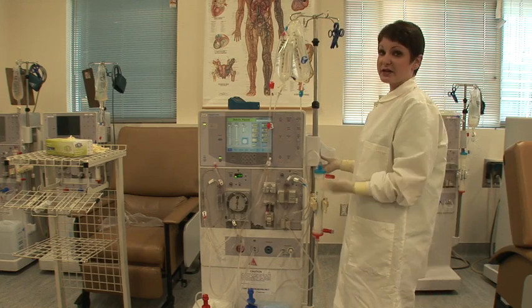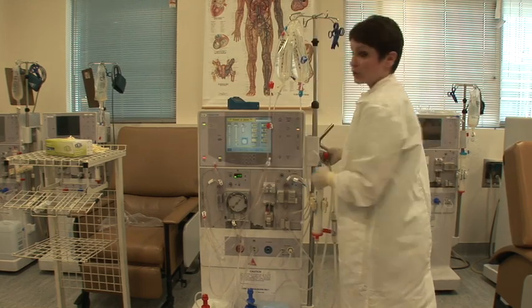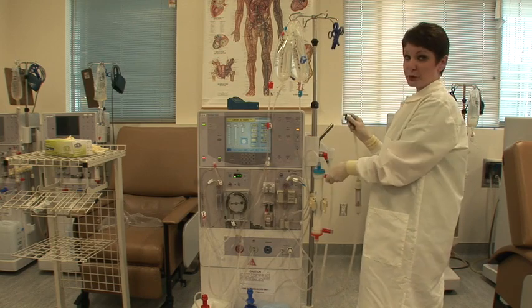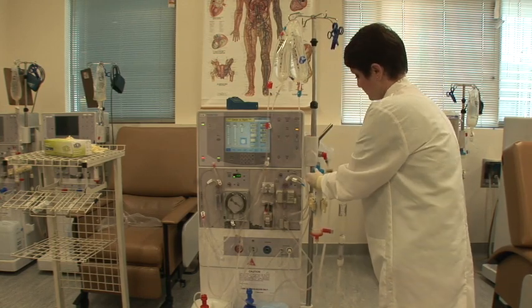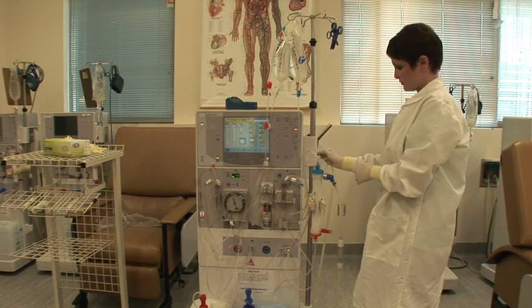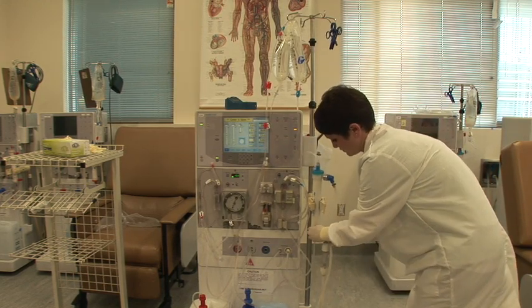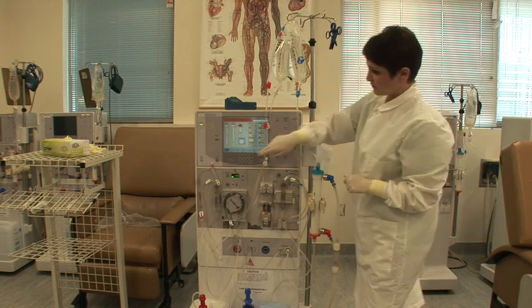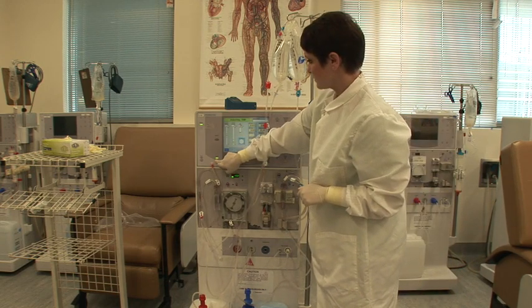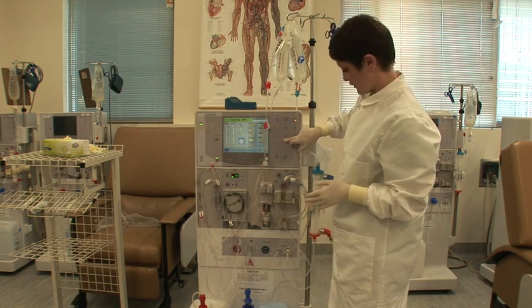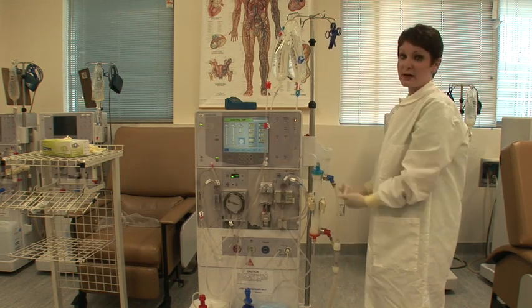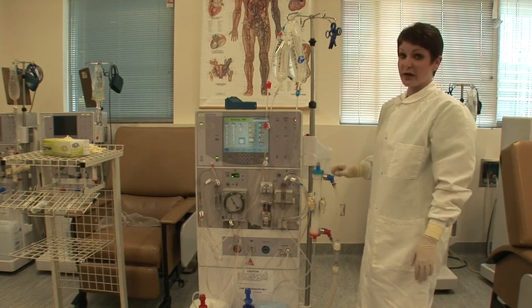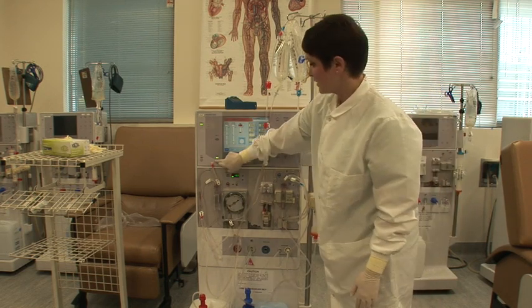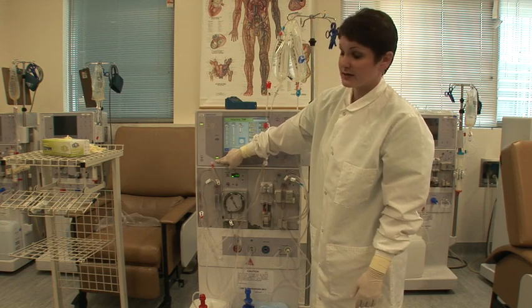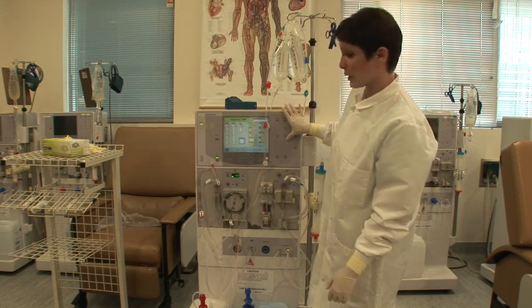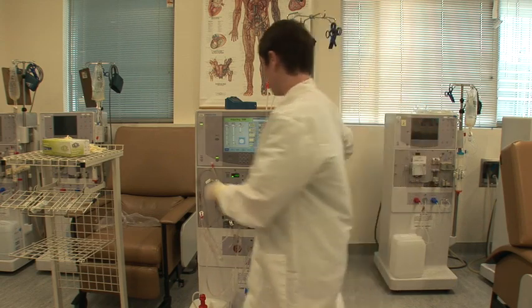At that point, it is safe to connect your dialysate to your dialyzer. So it's simply matching blue to blue, red to red. You're going to expect some fluid to come out of here because of the fact that your blood pump is flowing, the fluid's coming out of your dialysate ports in your dialyzer, as well as your Hansen connectors. Now that my Hansens are connected, my machine is going to give me all sorts of trouble until we get our transducers plugged in, which is the next step.